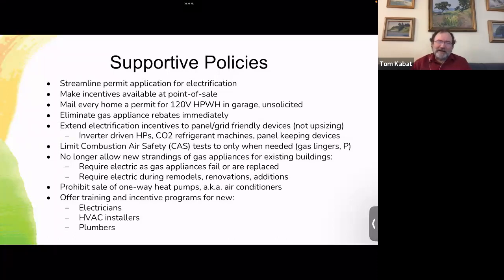Extend electrification incentives to cover panel-friendly and grid-friendly devices, not upsizing of panels. There are incentives for upsizing, but that's not the right thing to incent—you want to incent solving the problem, not upsizing the panel. Upsizing is one way to fit on, but optimizing to fit within the existing panel is a more grid-friendly and cheaper way, as shown earlier. Also expand incentives to cover different solutions like inverter-driven heat pumps, CO2 refrigerant heat pumps, and circuit sharers or circuit pausers—panel-keeping devices. So don't incent the upsizing, incent the alternatives to upsizing.